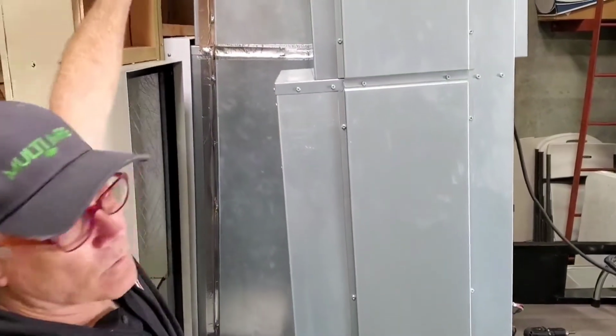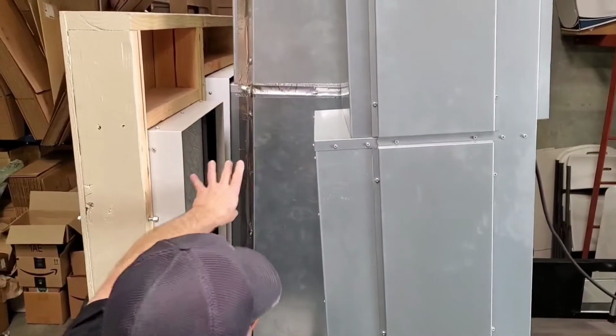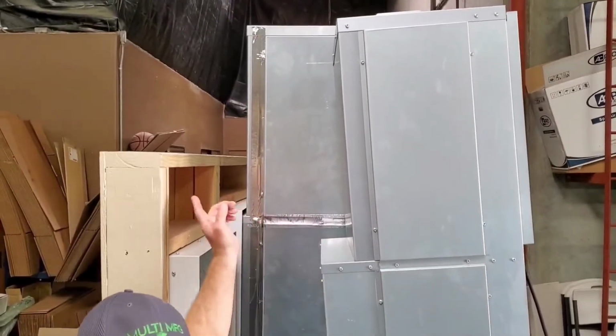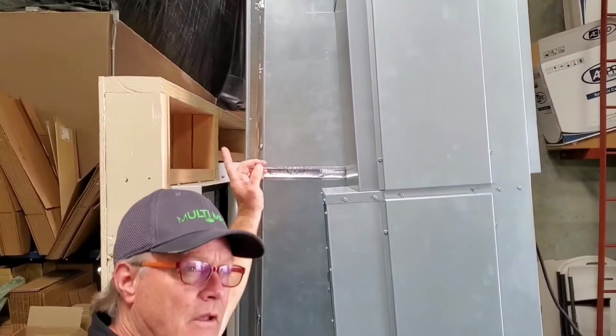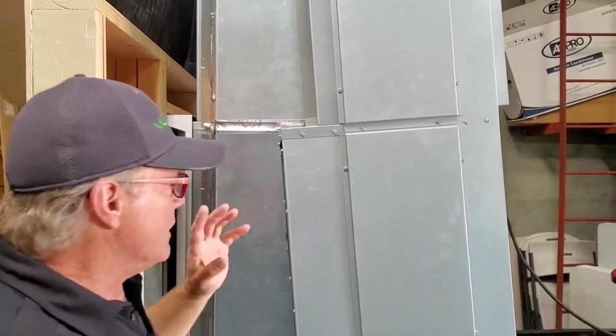Okay, first thing you do is you get the First Company unit out or the Amana unit out, and in doing so, up on top you're going to have ductwork. It's not here because this is a display trailer, but you'll disconnect the ductwork off the top in the closet. Put a metal strap on it, something to hold it up so it's not going to fall. Disconnect your electrical line voltage, low voltage, and then slide the unit out.